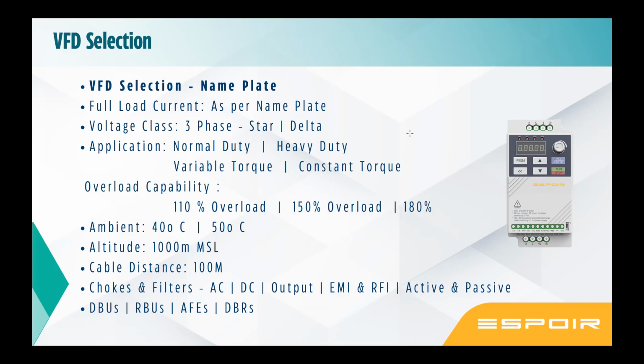Then there is something called the active and passive filter. I'll tell you one thing. VFD is a harm to the grid. Okay, VFD is a big harm to the grid. It is a generator of harmonics, not just a VFD. Any equipment which has a rectifier, wherever you convert AC into DC, it generates harmonics. What level of harmonics, what impacts, it is a different topic to address. I'll just touch upon 5th and 7th harmonics as the major harm. 5th generally disturbs the grid, 7th disturbs the system. Say you are supplying this VFD to a hospital where HVAC systems are there. This drive generates harmonics such that all the scanners will start working erratically.